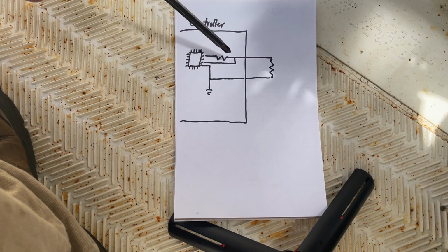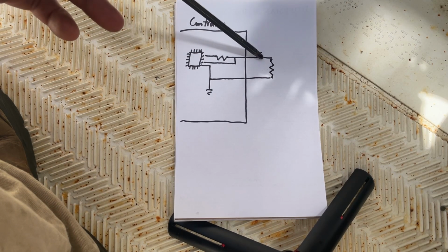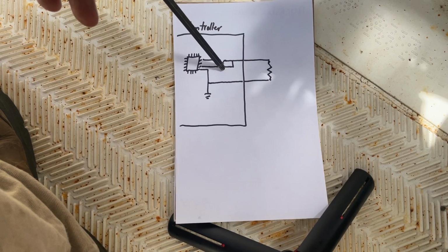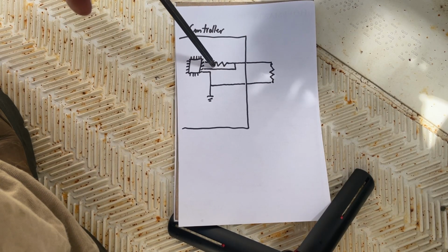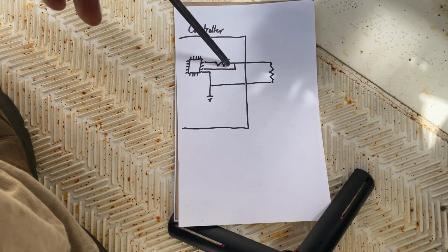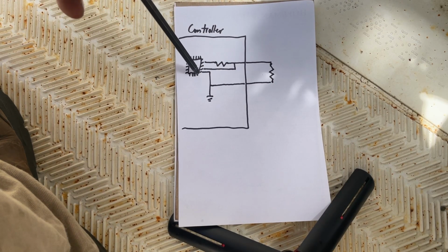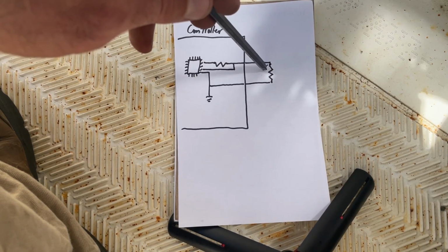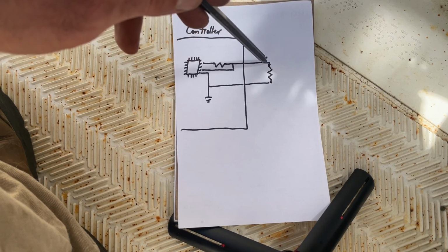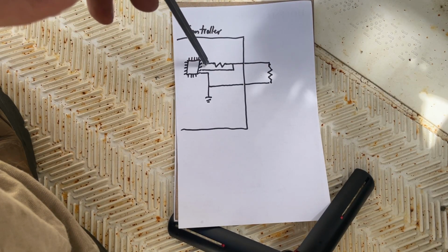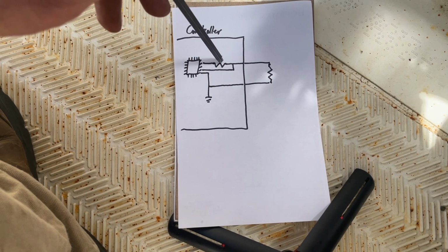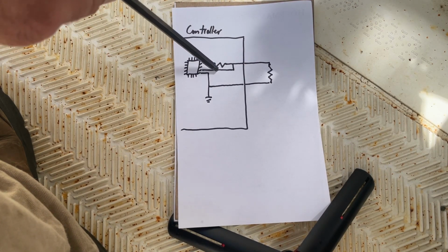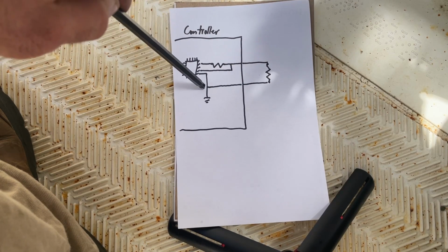All right. And this is also why you can short these wires out on a controller without any fear of damaging the circuit board, because all that's going to happen is that your voltage is going to drop completely across this resistor. So what the IC is going to see right here is just 0 volts. And then it will know that this is shorted. If this is open, it will also know that, because what it will see is full logic voltage going through this resistor and back to the IC, because there is no voltage drop when there can't be current flow, right?